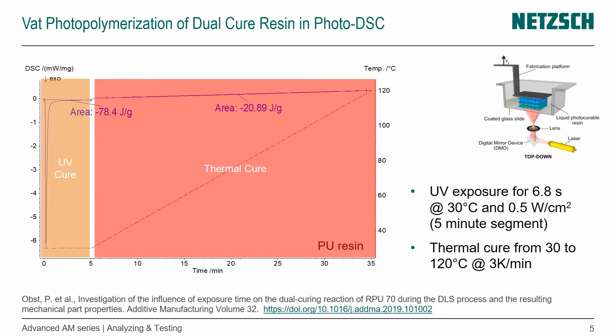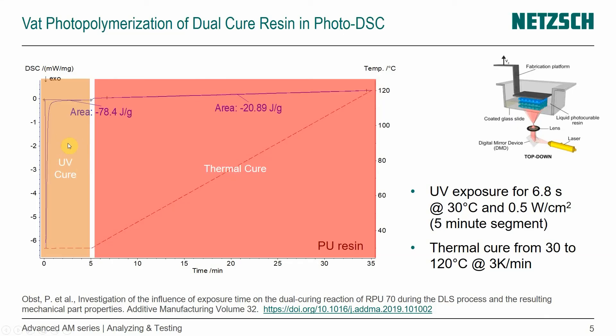So how does something like that look? In this case, I'm showing you the measurement of a dual-cure resin that we measured in this photo DSC, the Phoenix, which would be representative for digital light processing, because it's the dual-cure resin for that process. What we did here — I'm just showing that briefly — we had a UV curing segment and a thermal curing segment afterwards. We used 6.8 seconds UV exposure at 0.5 watts per square centimeter. We waited for the full five minutes, and then we increased the temperature from 30 to 120 degrees C at 3 Kelvin per minute. So UV cure followed by thermal cure for a polyurethane resin.